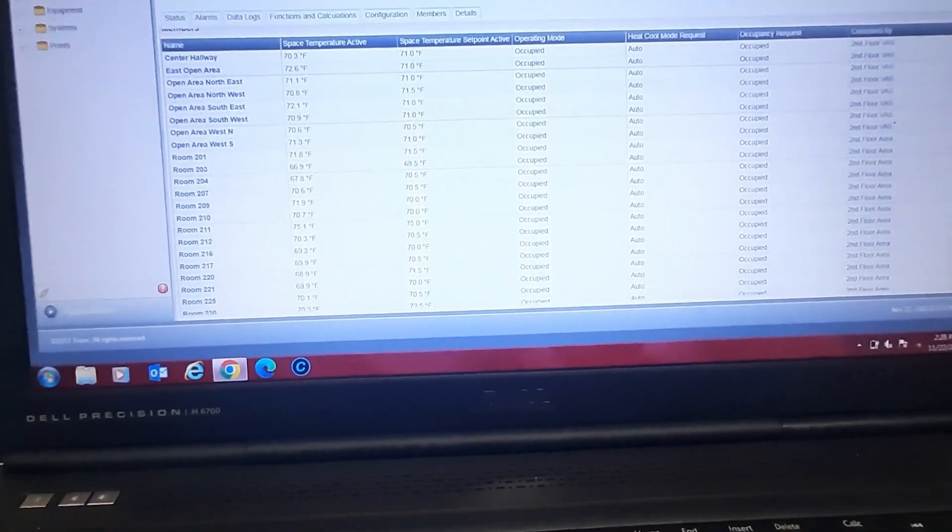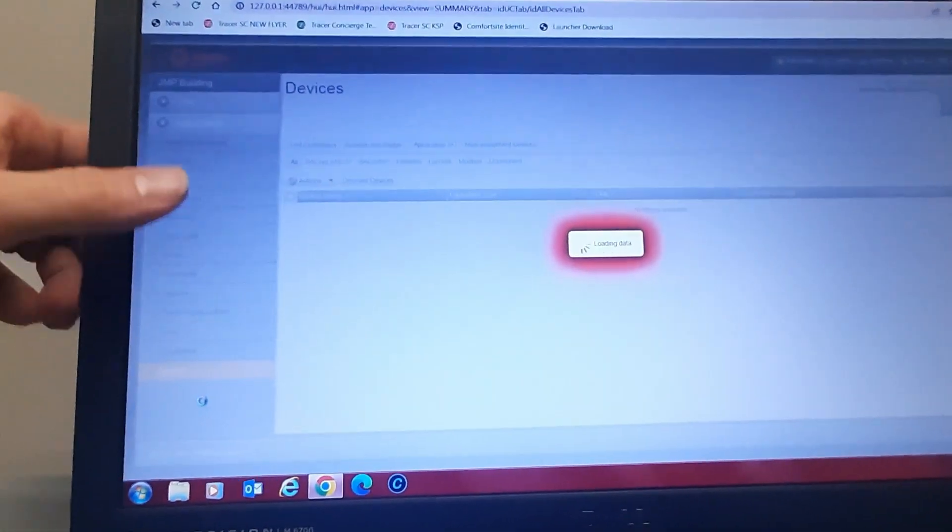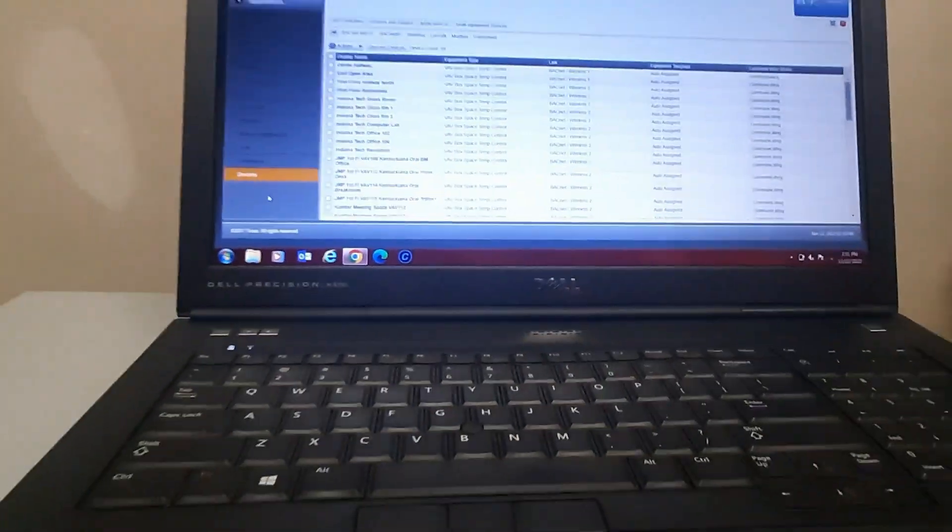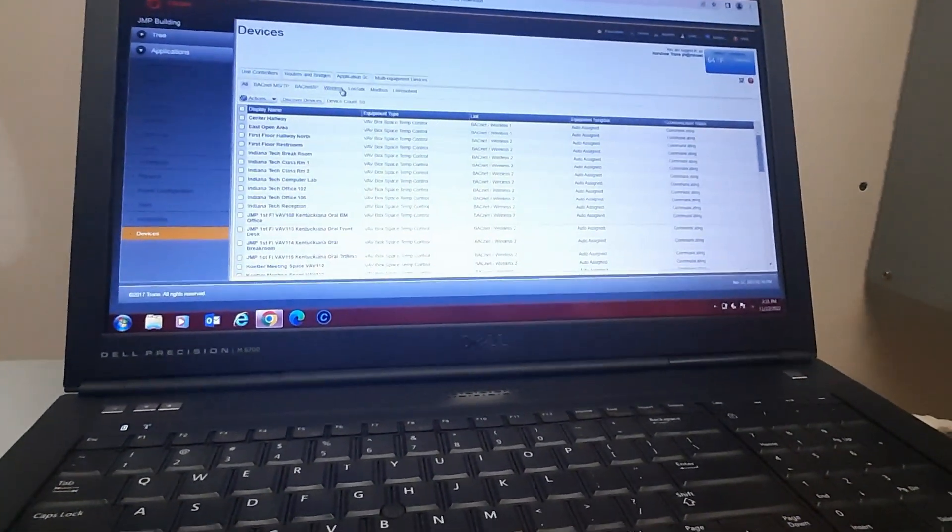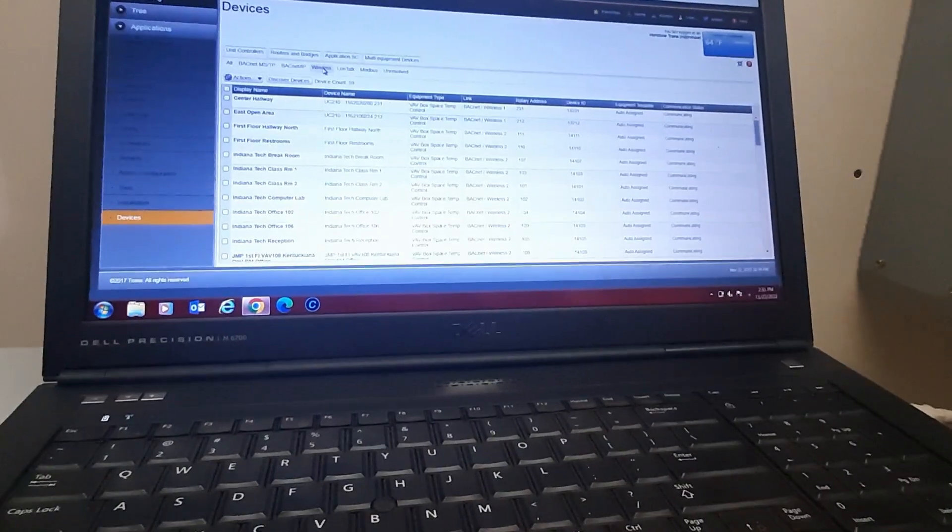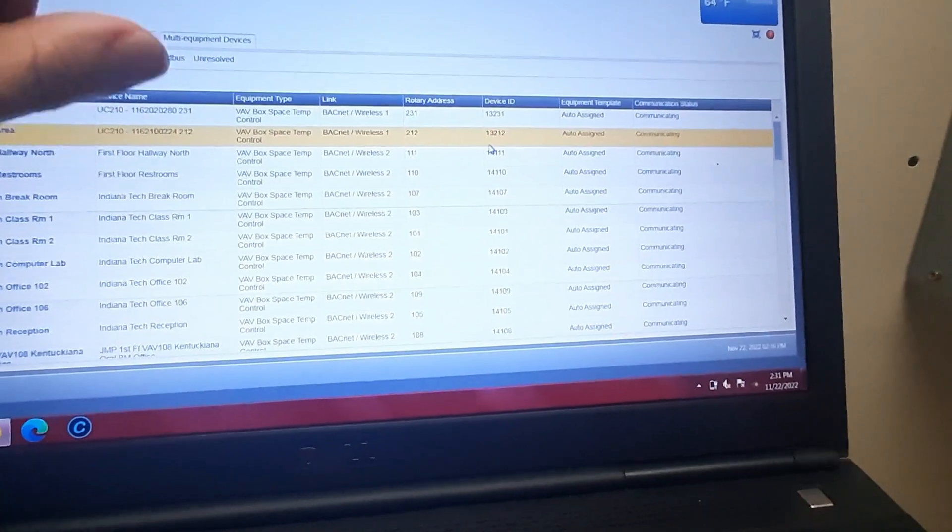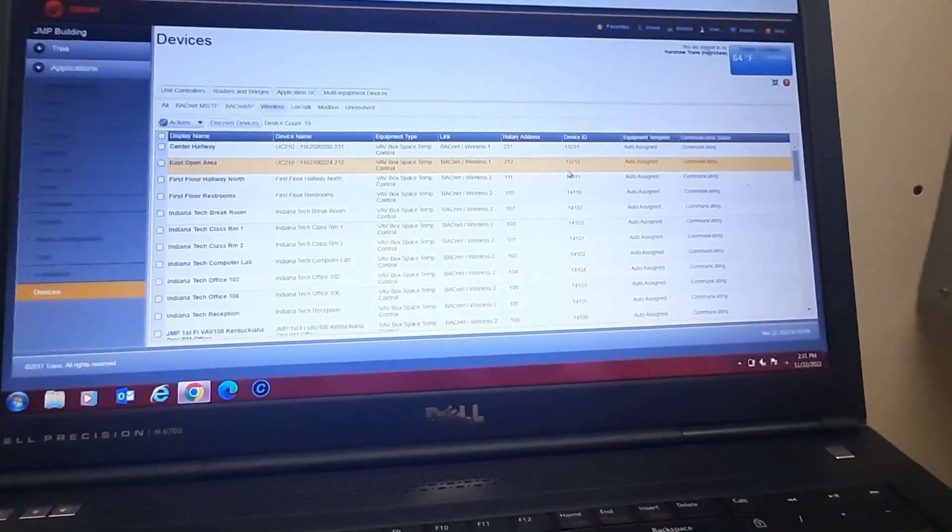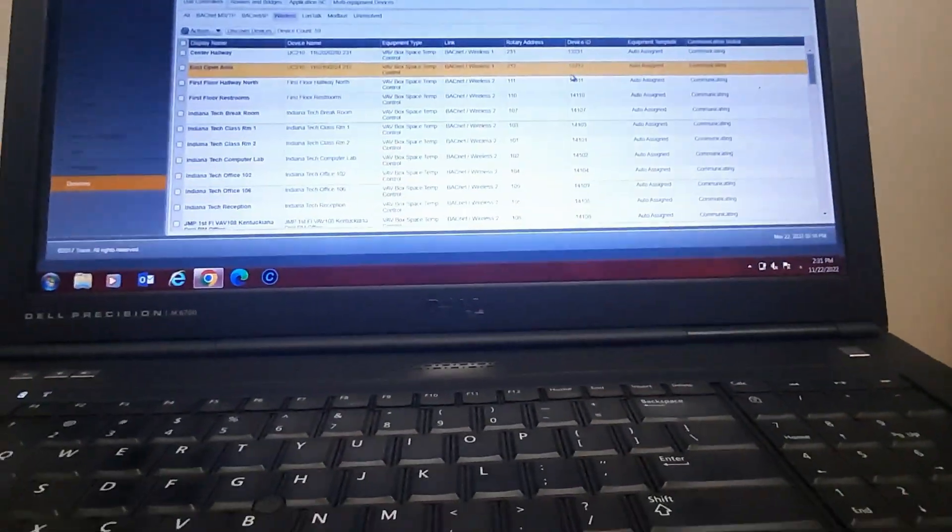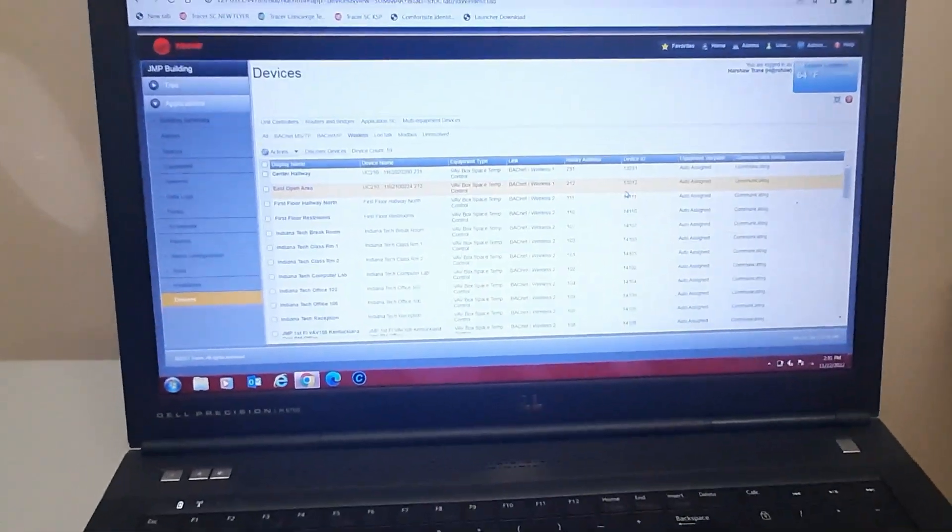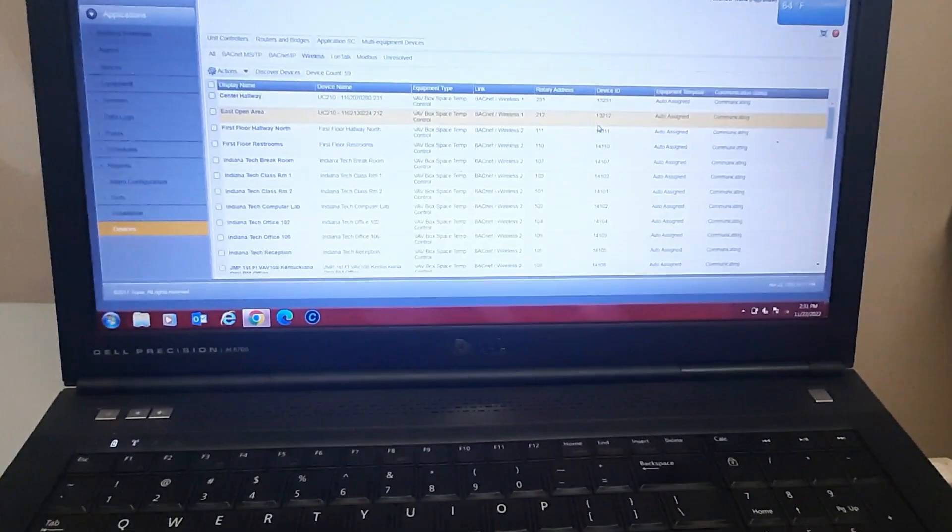So I'm going to go verify that that address is correct on the stat. So open my tree over here and went to devices. Devices is going to pull up all my devices and it should give me addresses. Let's see, this is wireless, so I can see my rotary address is there, so I can try to locate them that way and see if maybe I've dropped one. Although the thermostat didn't have an error code or anything on it, so I don't think I dropped a stat. I think it's just labeled wrong.